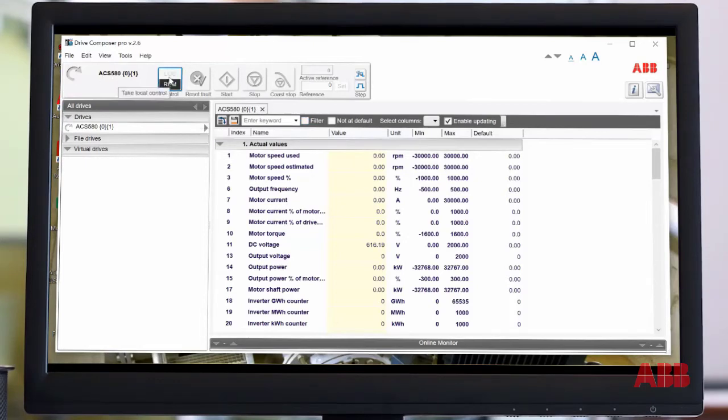And in order to start the drive, because we're not using a keypad, we're using Composer as an interface device or a keypad, if you will, I'll click on Local, and then we have the capability of a fault reset, starting the drive, stopping the drive, and so forth. So if we start the drive and give it a speed reference of, let's say, 30 hertz, we'll go up to speed now.